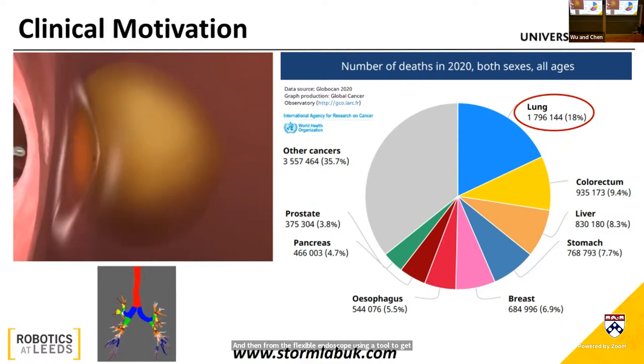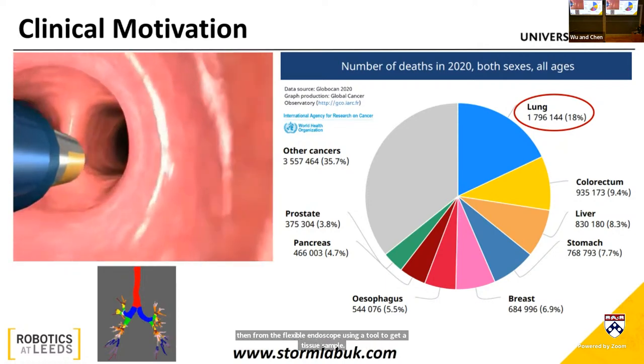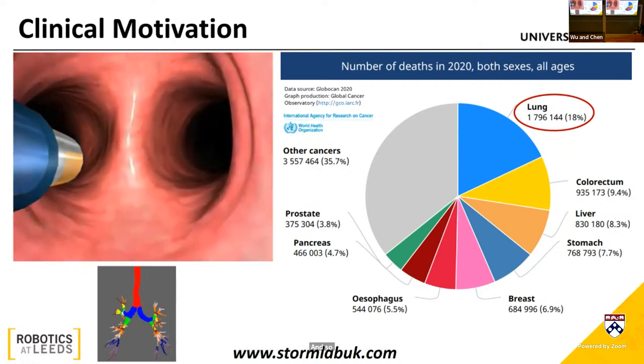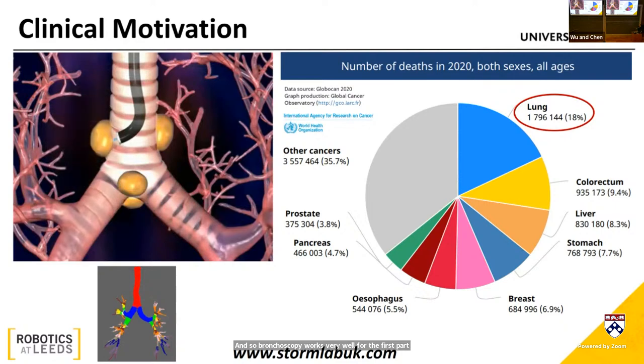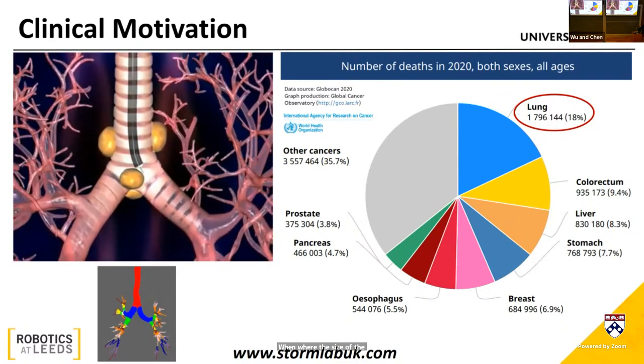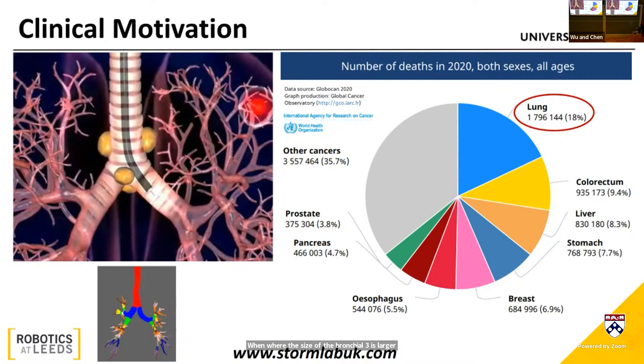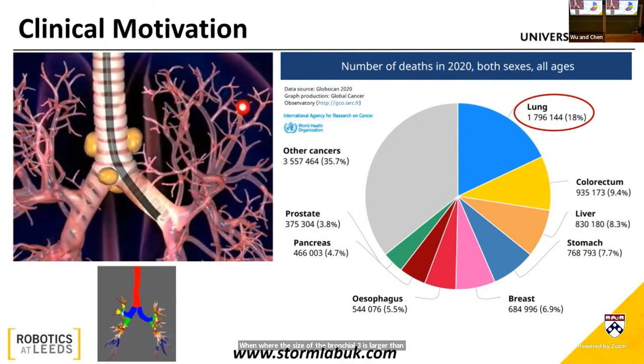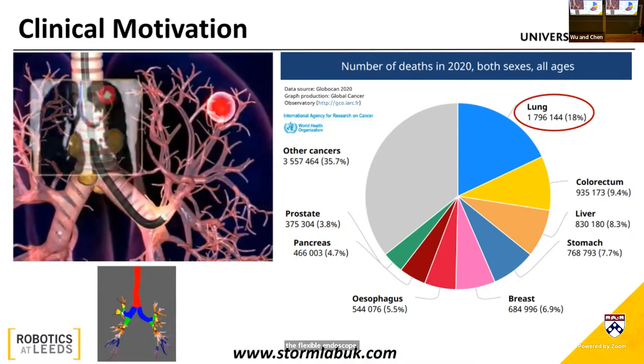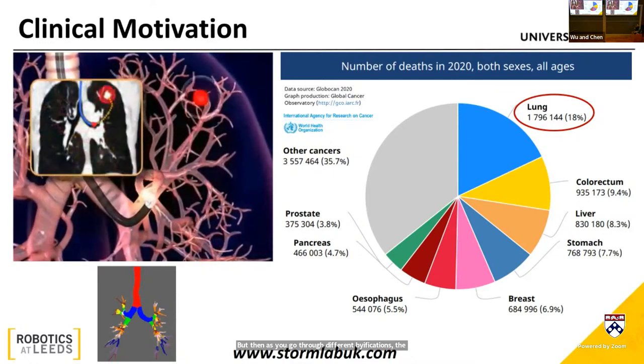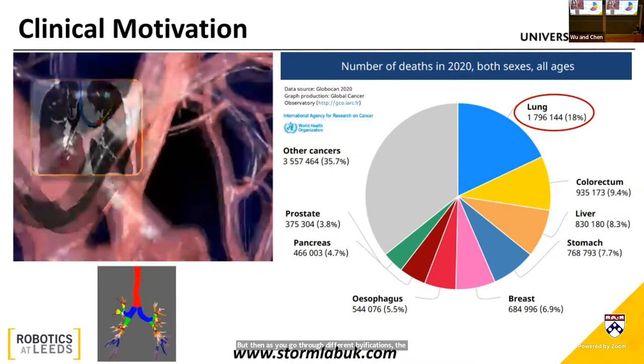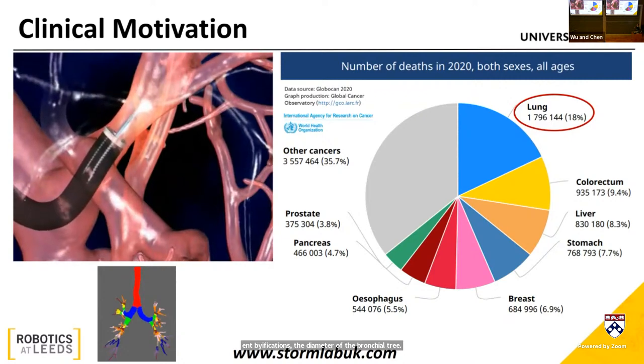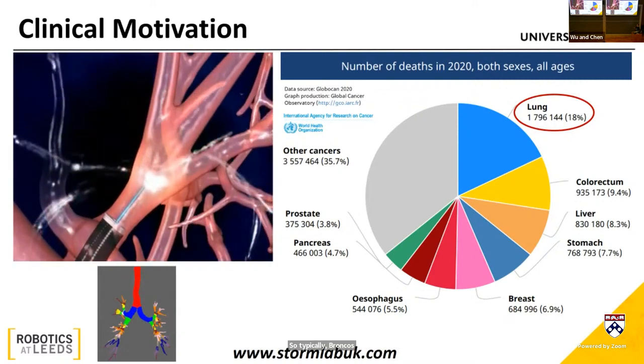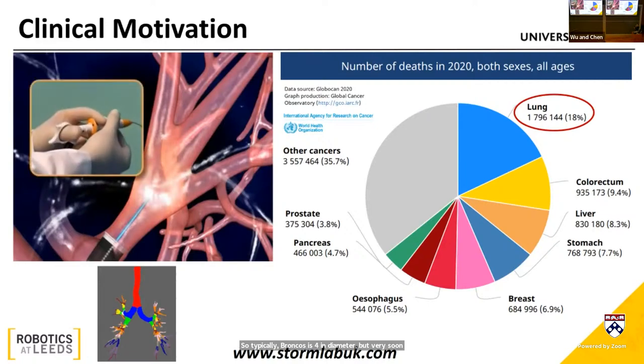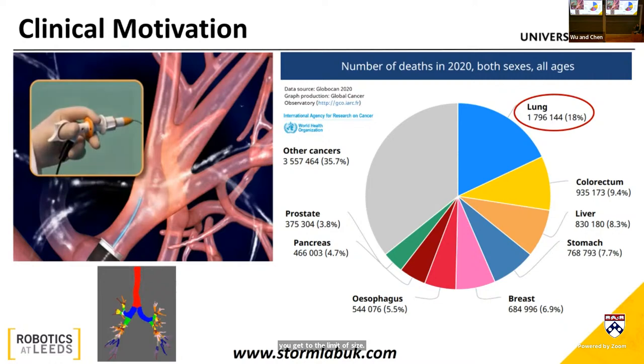Bronchoscopy works very well for the first part of the bronchial tree, where the size is larger than the flexible endoscope. But as you go through different bifurcations, the diameter of the bronchial tree gets smaller and smaller. Typically a bronchoscope is 4 millimeters in diameter, but very soon you get to the limit of size, and the flexible endoscope cannot progress any further.